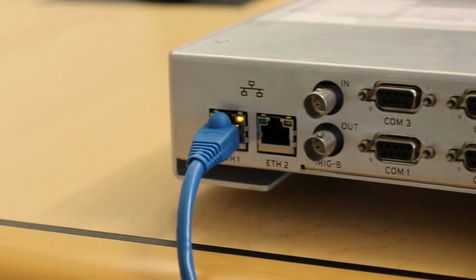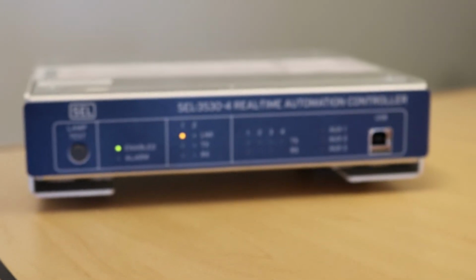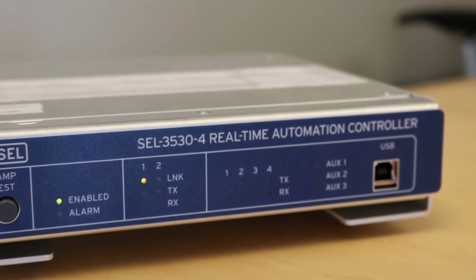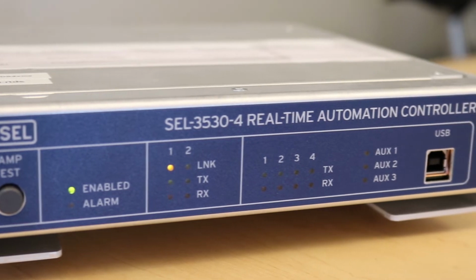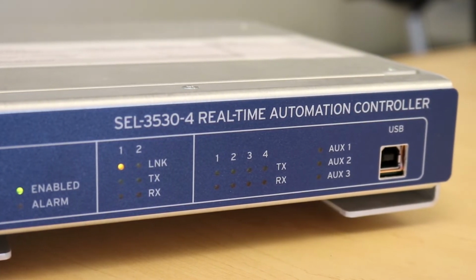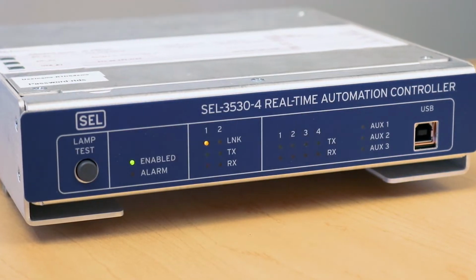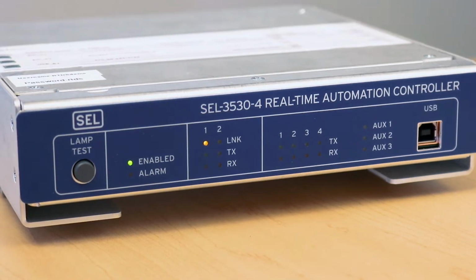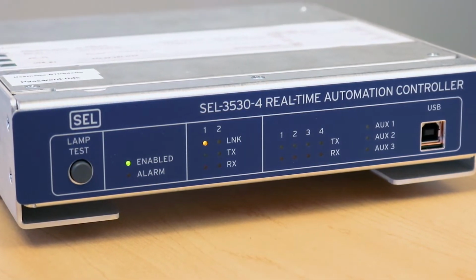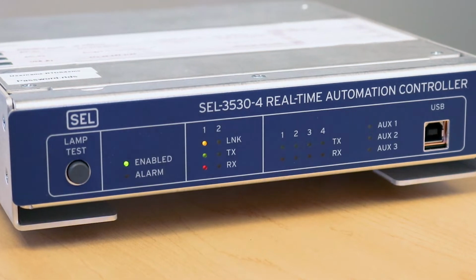In this particular hardware-in-the-loop testbed, the device under test is a commercial real-time automation controller, which might be deployed as a secondary-level microgrid control system. Here, it's programmed to provide load-shedding functionality in order to restore the microgrid frequency in the event of islanding-related imbalances or other issues.